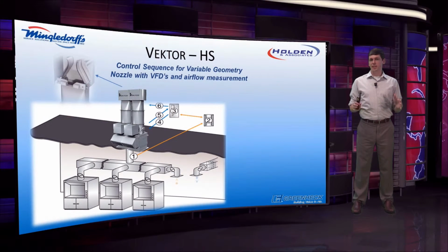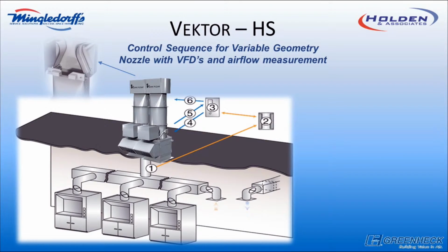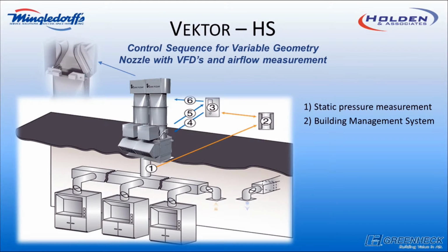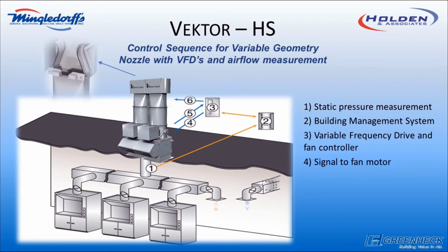Now we'll have a Vektor HS control sequence. This image shows a multiple hood situation where demand may vary based on how many hoods are active and what's actually going on in the space. Point 1 would be a static pressure sensor connected to a BMS. The static pressure sensor will tell us what's actually going on in the exhaust ductwork and how much demand is needed. The BMS then will relay to the VFD and the variable geometry nozzle controller about what's going on, what needs to be done. This controller and VFD will then control the fan motor, telling it to speed up or slow down based on the demand in the space.